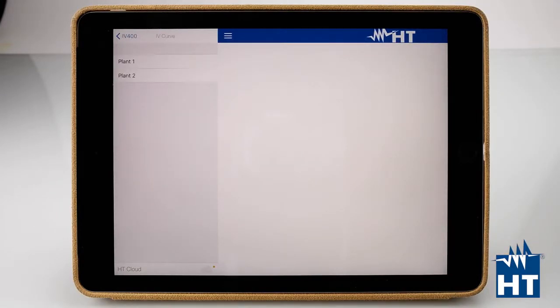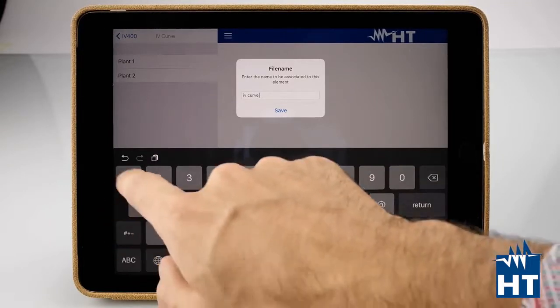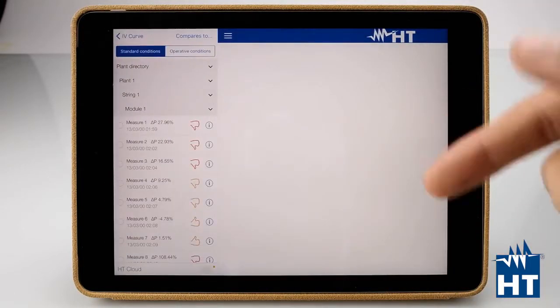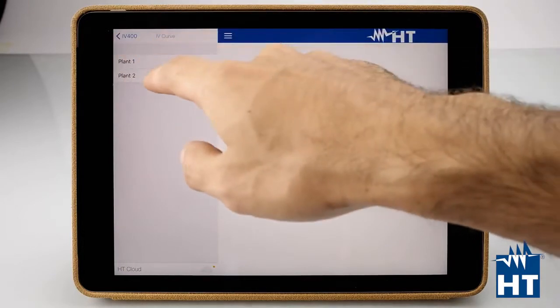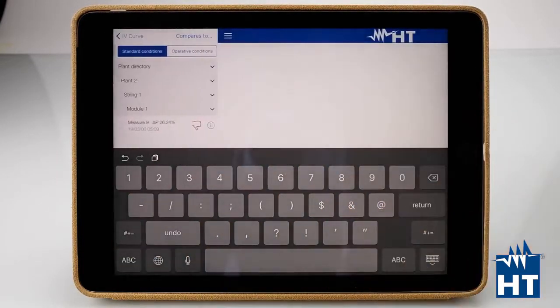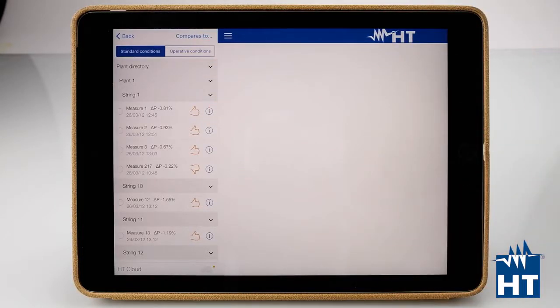Let's download some measurements. We have Plant1 and Plant2 that we already named on the IV400 before. So Plant1 — the curve data is now downloading. We can give it a name, IVCurve1, and save. Now we have everything about this measurement campaign. Let's download the second one as well — IVCurve2. Now we can go back to the curves. Here we have Plant1 that we downloaded, and we can find measure 1, measure 2, measure 3. Each measure is an IV curve.